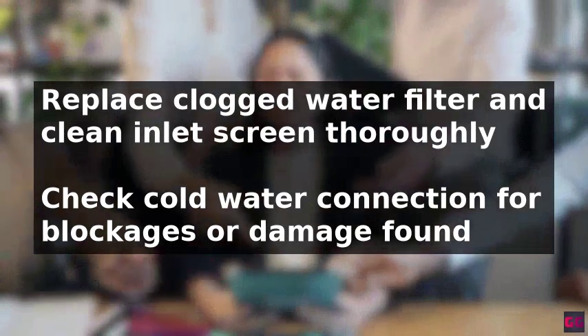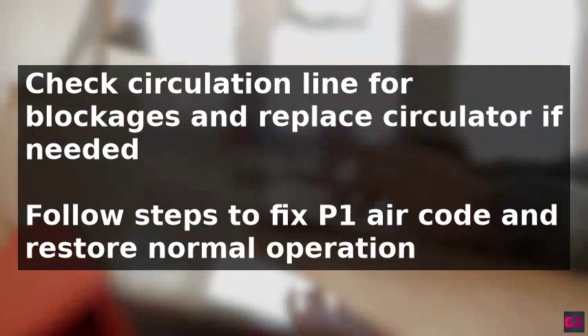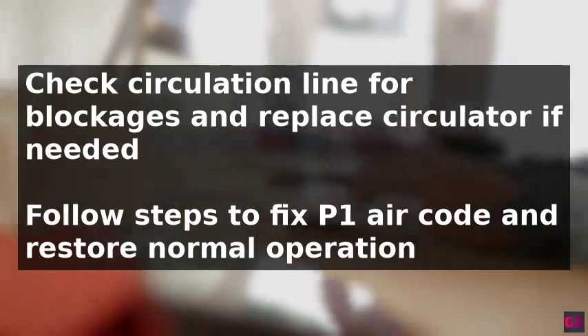Replacing the water filter and cleaning the inlet screen can help resolve the issue. It is also necessary to check the cold water connection and the circulation line for any blockages, and replace the circulator if needed. By following these steps, the P1 error code can be fixed, and the tankless water heater can operate normally again.